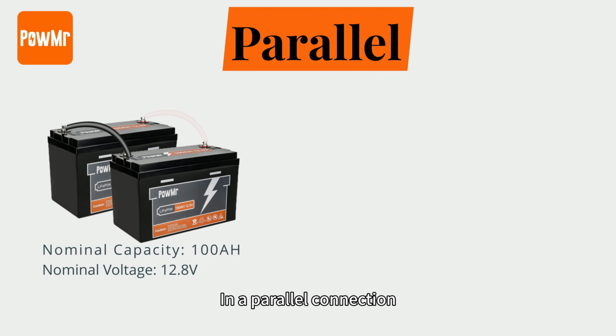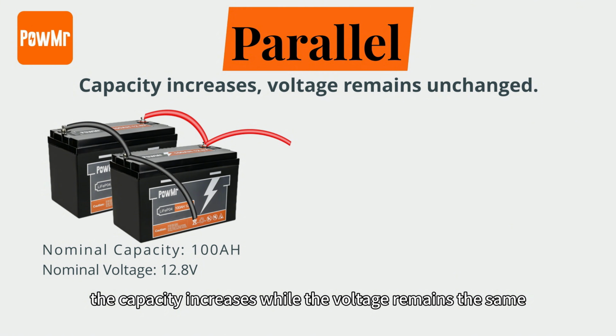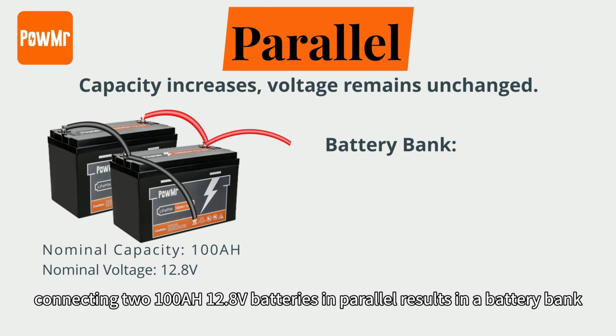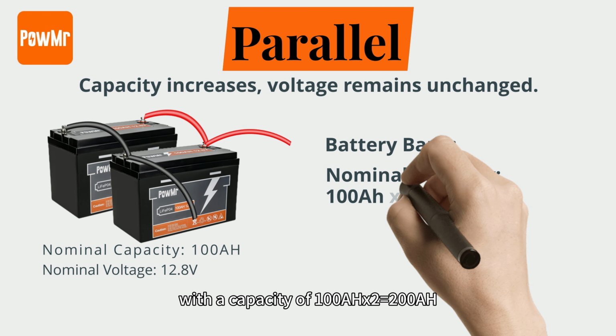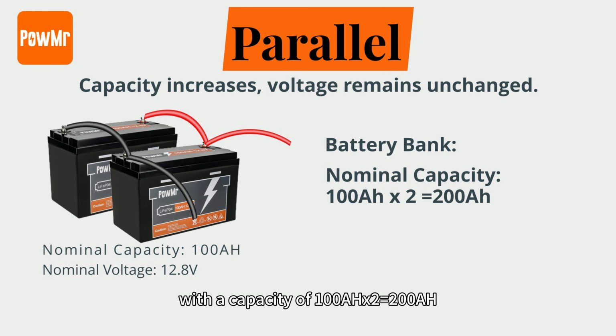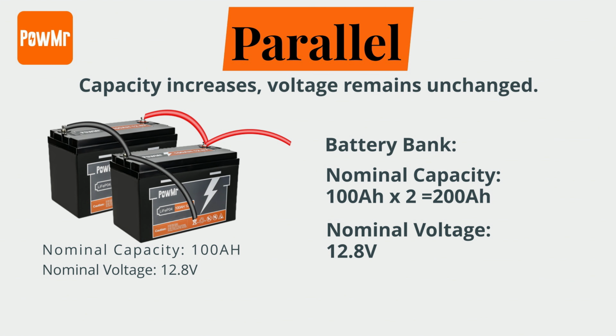In a parallel connection, the capacity increases while the voltage remains the same. For example, connecting two 100 amp hour 12.8 volt batteries in parallel results in a battery bank with a capacity of 100 amp hour times 2 equals 200 amp hour, while the voltage remains at 12.8 volt.